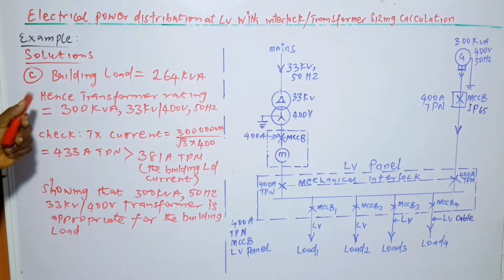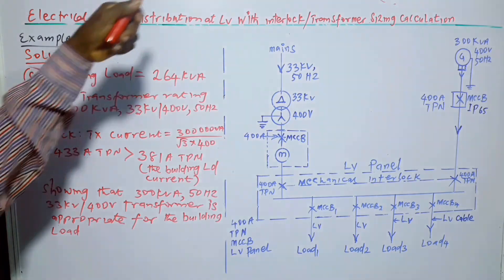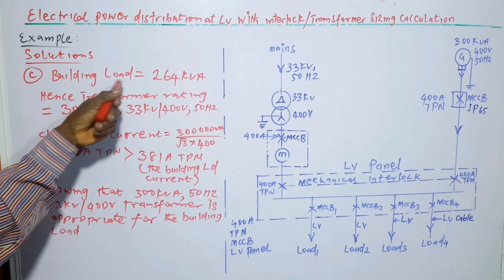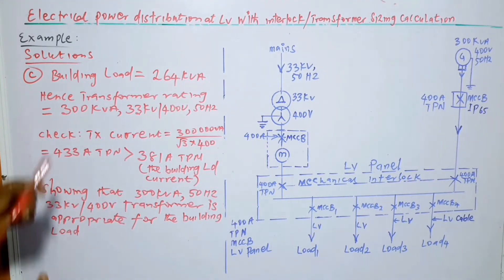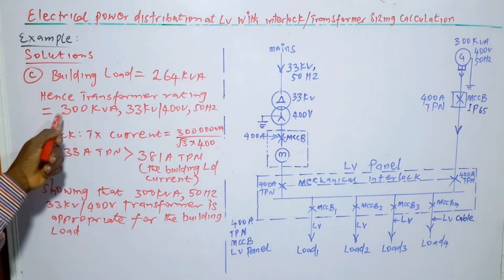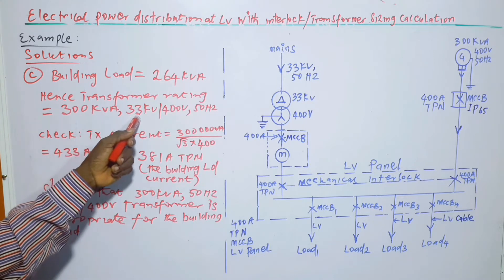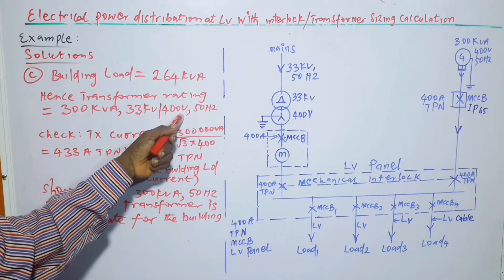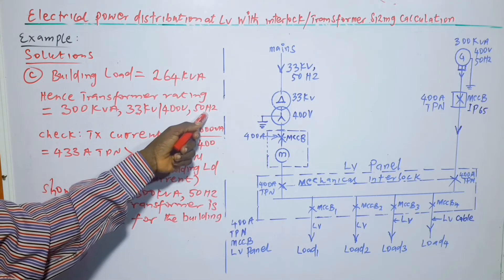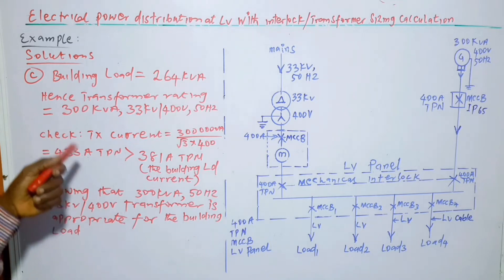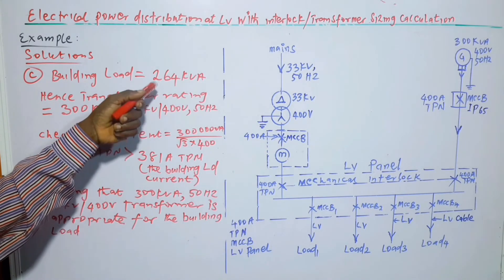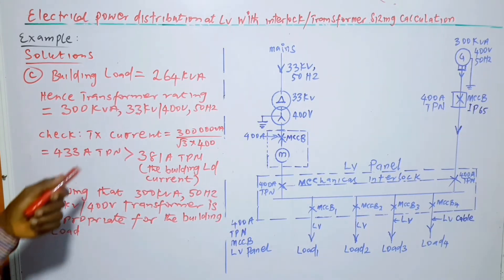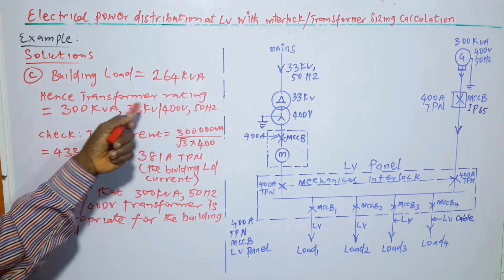Moving on, part C: to calculate the transformer rating. Building load is 264 kVA. Hence, transformer rating is equal to 300 kVA, 33 kV/400 V, 50 Hz. So we choose the transformer rating that is higher than the building load. So the next one is 300 kVA.